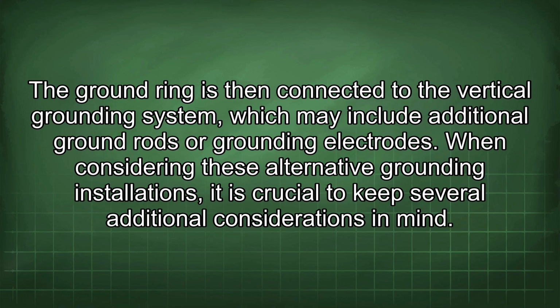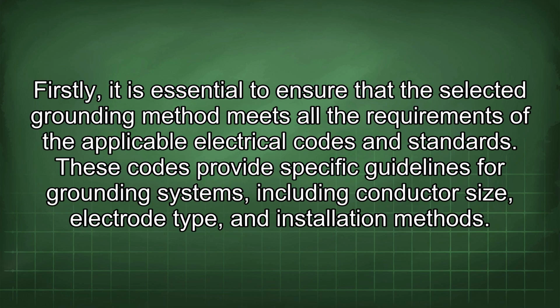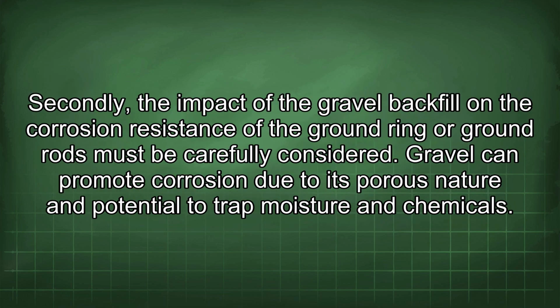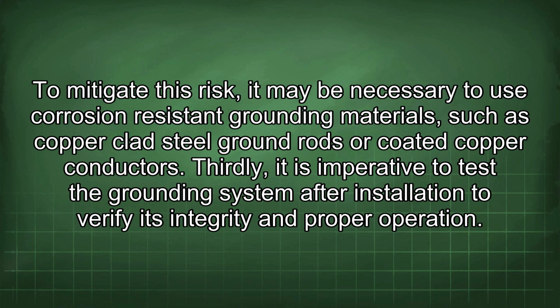When considering these alternative grounding installations, it is crucial to keep several additional considerations in mind. Firstly, it is essential to ensure that the selected grounding method meets all the requirements of the applicable electrical codes and standards. These codes provide specific guidelines for grounding systems, including conductor size, electrode type, and installation methods. Secondly, the impact of the gravel backfill on the corrosion resistance of the ground ring or ground rods must be carefully considered. Gravel can promote corrosion due to its porous nature and potential to trap moisture and chemicals.